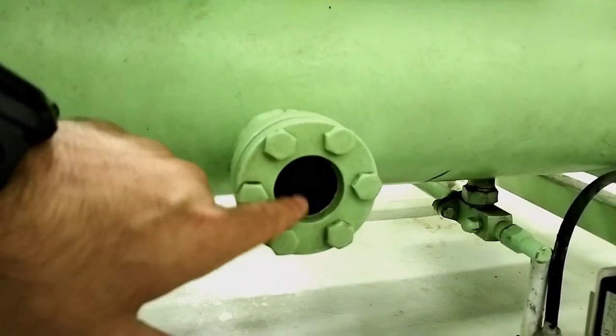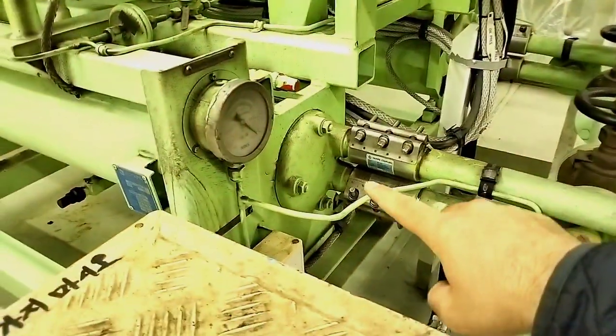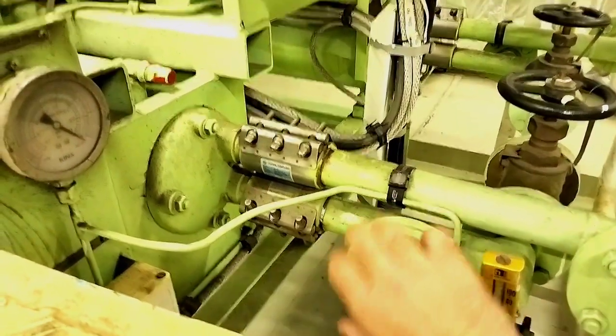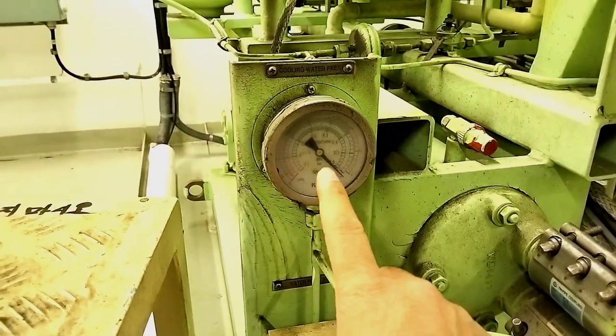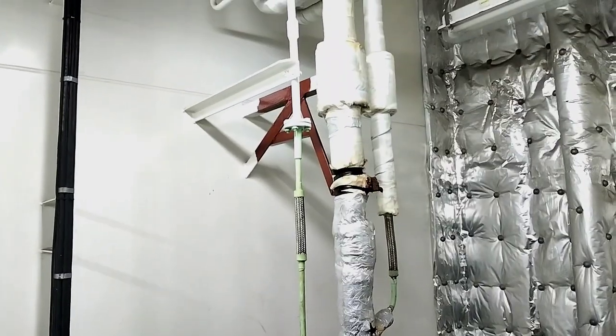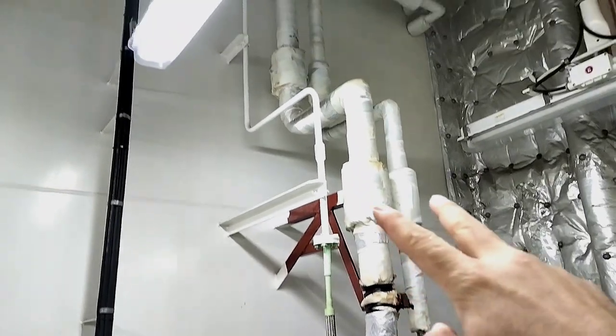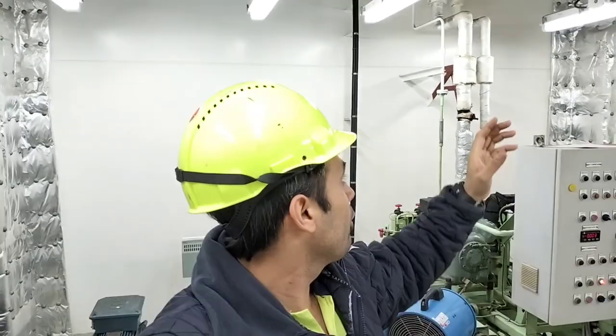This is the fresh water cooling pipe for the condenser — this is the fresh water inlet and this is the fresh water outlet. This is a thermometer, and here we have a cooling water pressure gauge and a cooling water pressure switch. And if you can see these two pipes, these two pipes are going inside the refrigeration chamber, which I will show you later. Now I will show you the second part of this refrigeration plant on another deck — that pipe is going to the refrigeration chamber, so let's go there for more clarity.